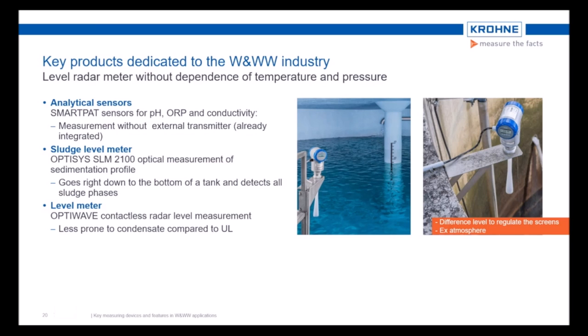Especially in wastewater applications, we often have a small foam layer on top of the surface, which is a sudden death factor for ultrasonics. Radar can easily measure through it due to the better measuring dynamic. A comparable effect occurs with condensate within the manhole or installation spots. So radar is much less sensitive to losing the signal compared to ultrasonic. Generally, this 24 GHz device has a special drop antenna with a small beam angle to be installed in narrow applications. IP68, NEMA 6P and the free field certification, which is meant by LPR, level probing radar, as well as the TLPR, tank level probing radar, are of course standard.